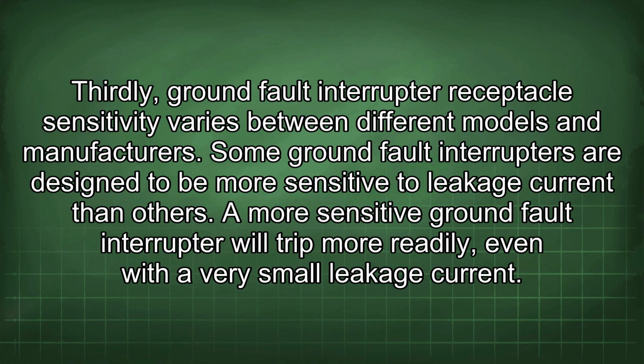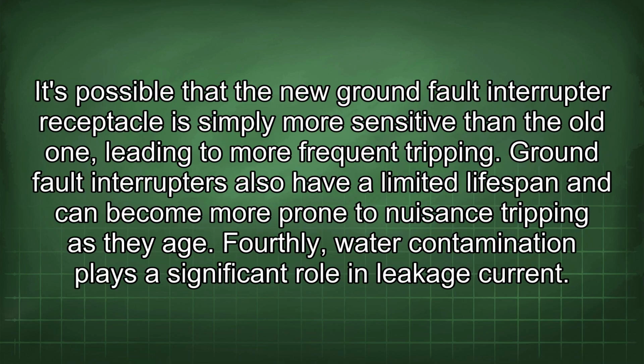Some ground fault interrupters are designed to be more sensitive to leakage current than others. A more sensitive ground fault interrupter will trip more readily, even with a very small leakage current. It's possible that the new ground fault interrupter receptacle is simply more sensitive than the old one, leading to more frequent tripping. Ground fault interrupters also have a limited lifespan and can become more prone to nuisance tripping as they age. Fourthly, water contamination plays a significant role in leakage current.